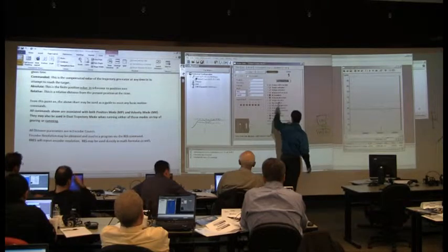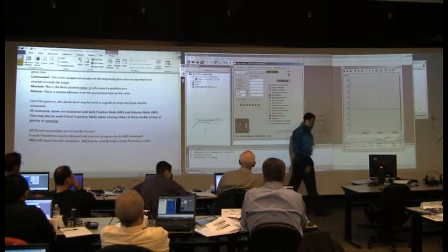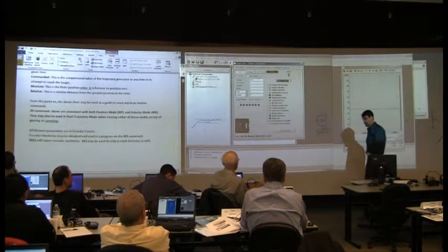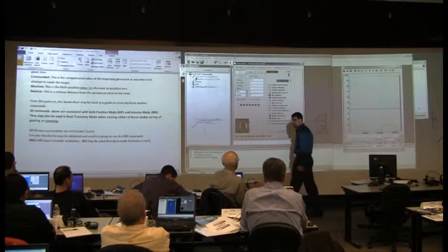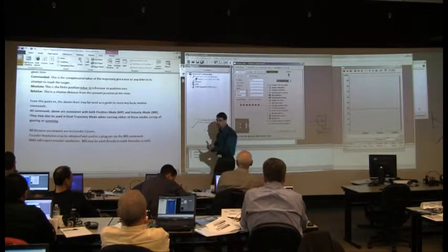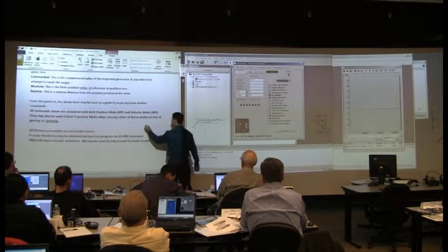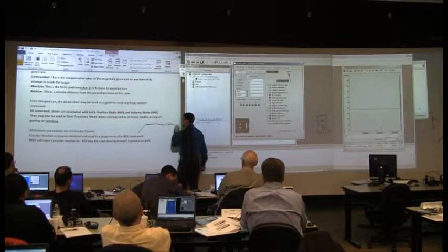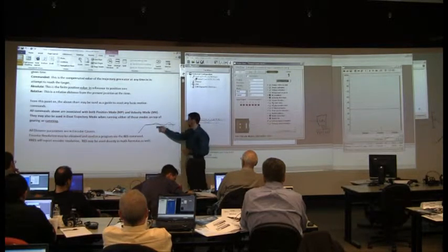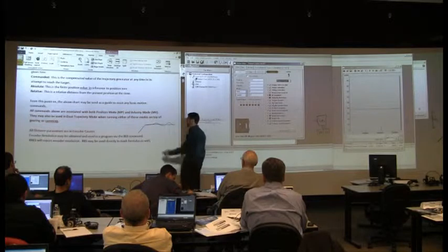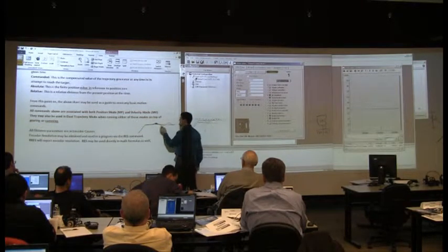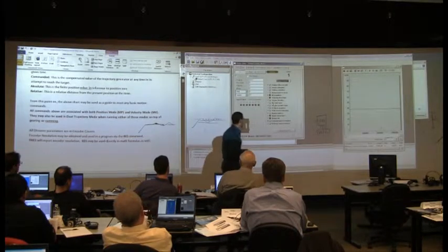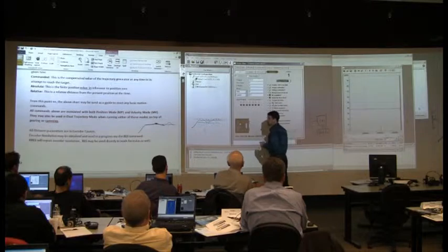Okay? You have something called velocity direction and torque direction. I had them add this in firmware probably 4 years ago when we first started doing Class 5. The reason being is you may want to know if you're driving forward or reverse. You may want to know, if you accelerate up to speed and you start getting velocity ripple due to changes in load, which side of the curve you're on. If you're going in the positive direction, the bit will be on. When you're going to the negative, it'll be off, for a given direction. That's what that's about.